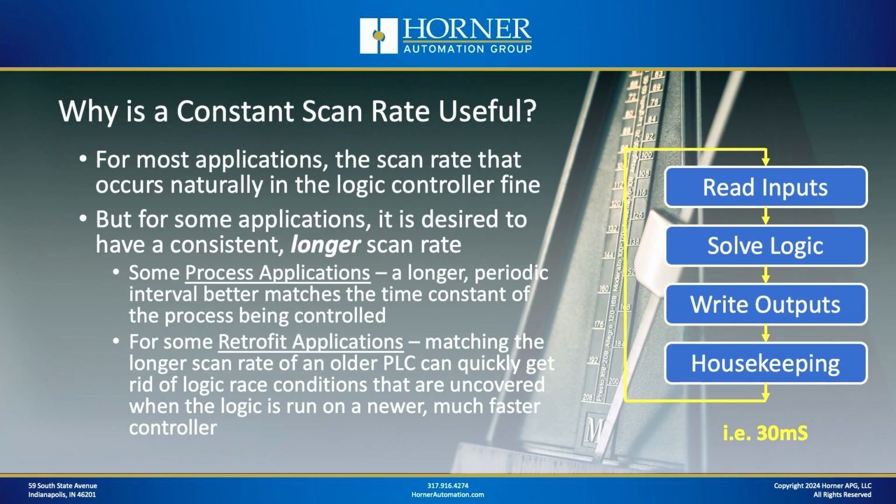Let's talk about process applications. Now, in some process applications, a longer solve interval on your entire logic program may more closely match the time constant of the process you're controlling. So that could be a scenario where lengthening to a constant, longer periodic scan rate might be good.